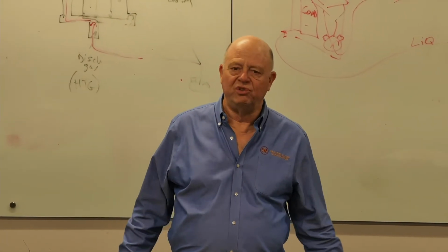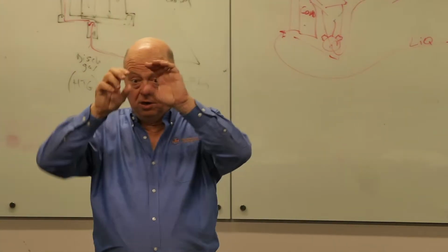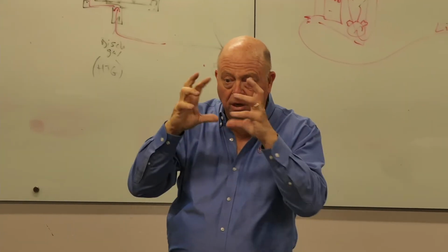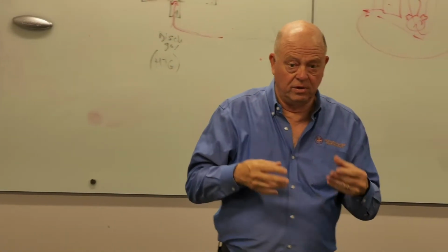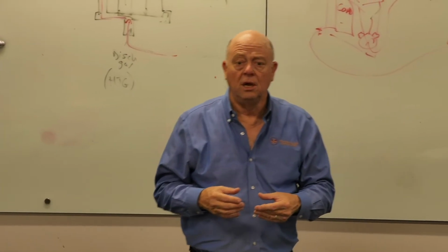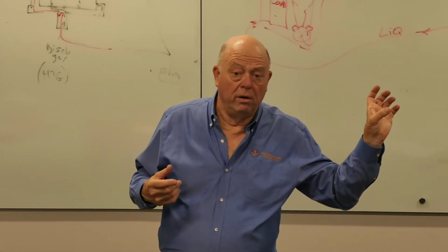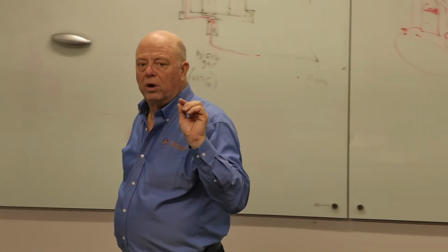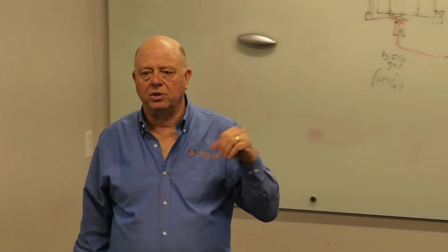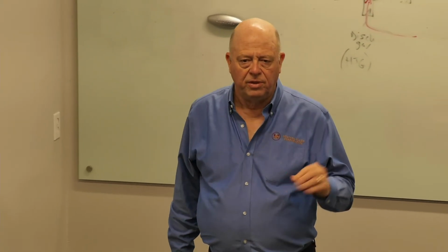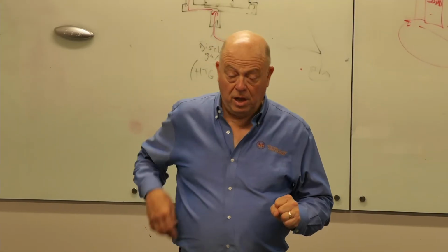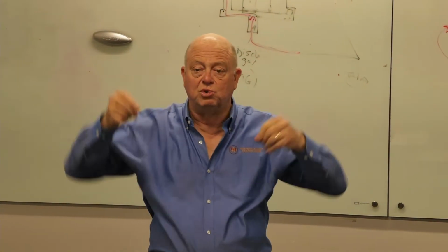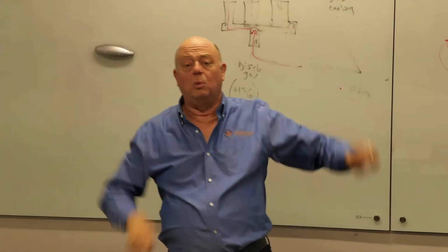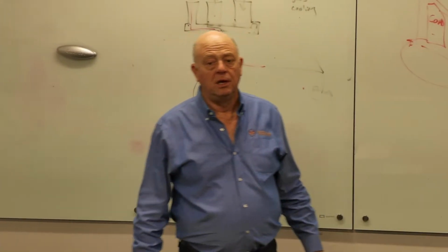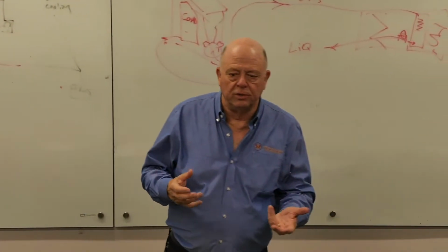Now, we just do it at the same time, but there's some more labor because you actually have to be good at brazing to replace one of those. You can't have the kid who's 1 year out of trade school do that usually. And you've got the part, whatever it costs. Where it gets to be real interesting is if it's more than 10 years old, I can almost guarantee you that reversing valve will no longer be available. They'll have a generic one you can use, but the pipe connections won't be the same. So now you've got to repipe everything. You can line up with one pipe, but the other 3 will be wrong, is usually kind of how it works out. So that's just a thing we run into.